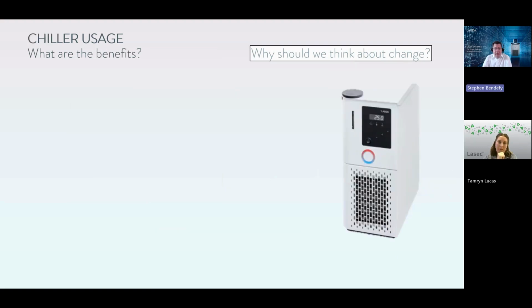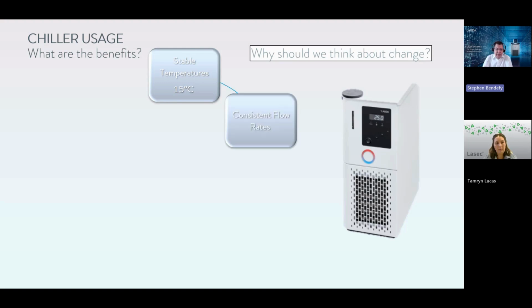So what are the benefits of using a chiller? It means that we get stable temperatures. We can dial in a temperature of, for example, 10 centigrade, 15 centigrade, and it will keep that temperature constant. That gives us repeatability, reproducibility, and constant cooling in our application. We have consistent flow rates, not influenced by whether it's daytime or nighttime or what other demands might be on the system.